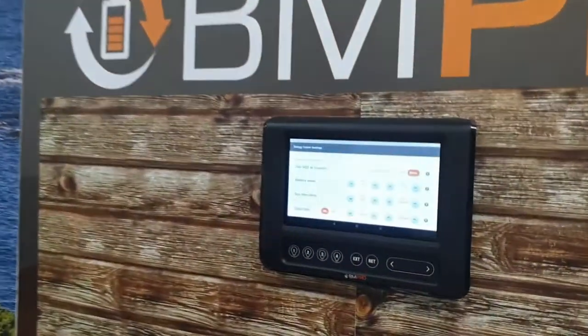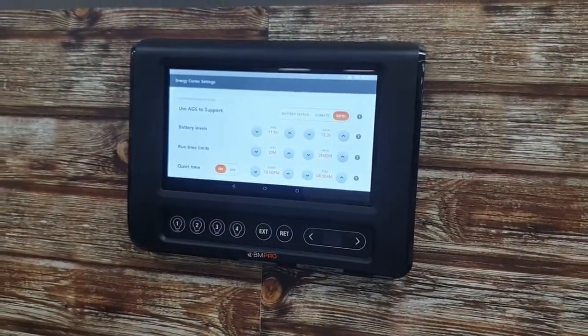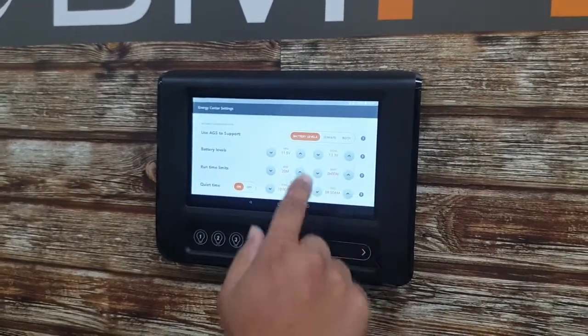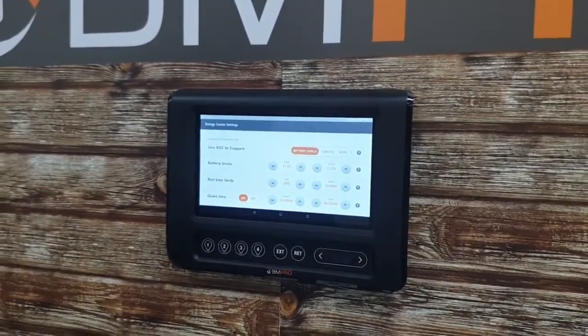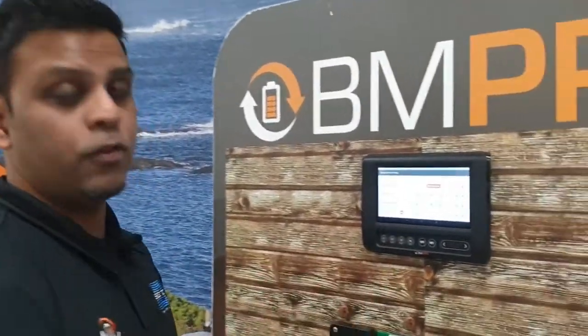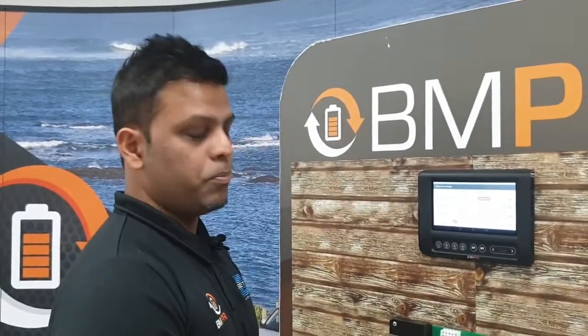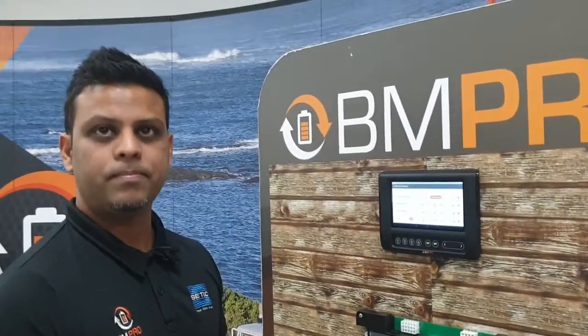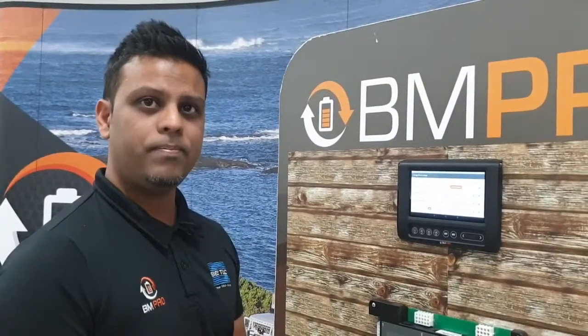The maximum run time is the time the user can set so that the generator does not run forever. For example, if the battery voltage stays at around 12 volts and never reaches the target, it will run for a maximum of two hours in this example. The same applies for temperature: if you've set 80 degrees Fahrenheit and you're not going to get there — perhaps because a door is left open — the generator will run its best and then turn off within this time limit.